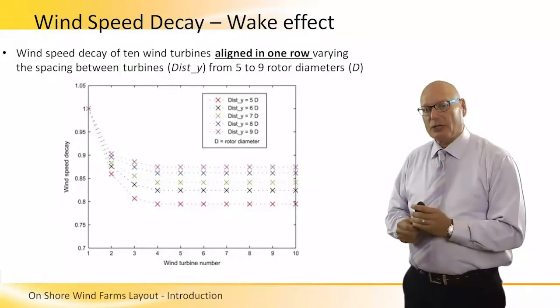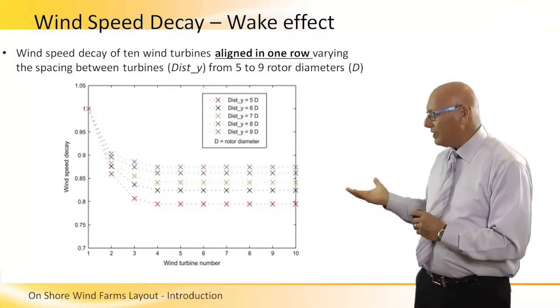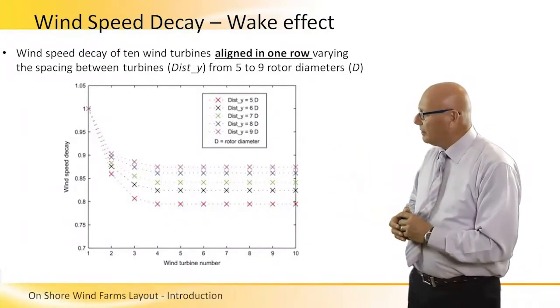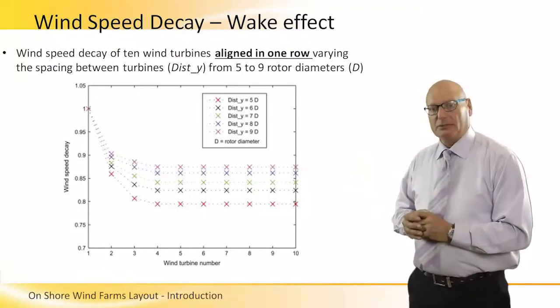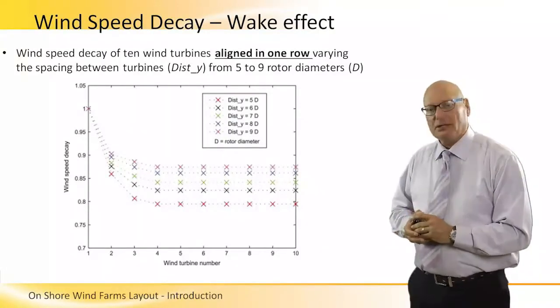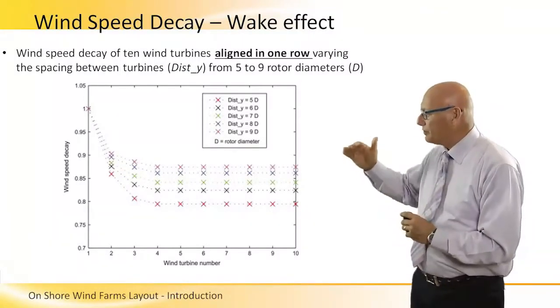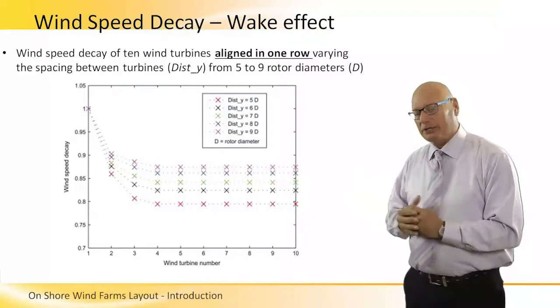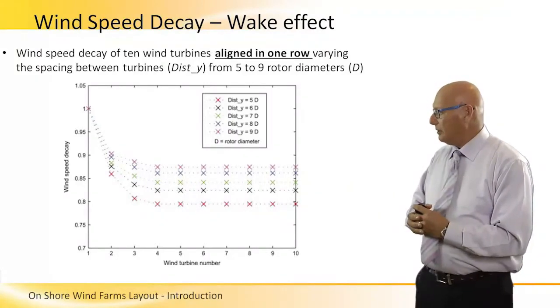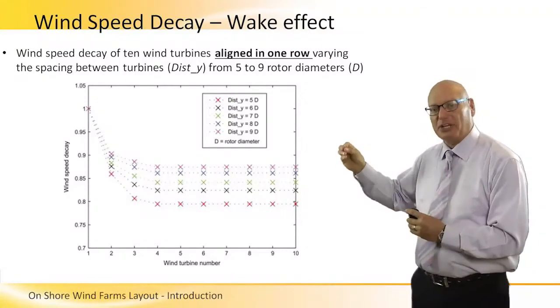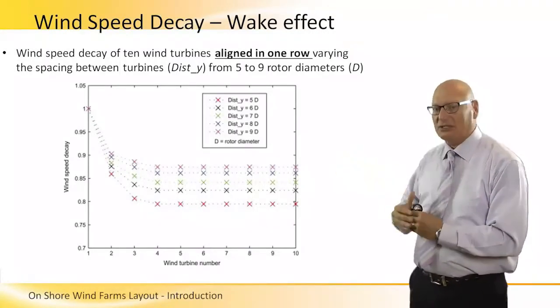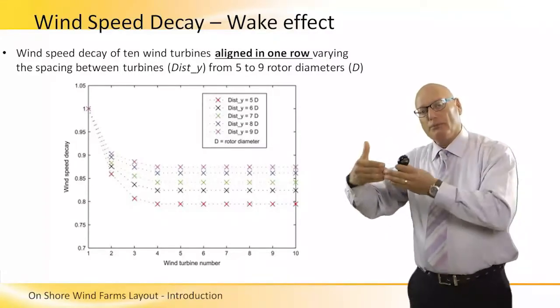This graph shows something very interesting. The horizontal axis is the number of wind turbines in a farm, and the vertical axis is the wind speed decay — the percentage of decay in wind speed as we increase the number of turbines and as we increase or decrease the distance between each turbine. We see five different examples: when the distance is five times the diameter compared to a distance of nine diameters, there will be a difference in the wind speed decay from the front row compared to the back rows.